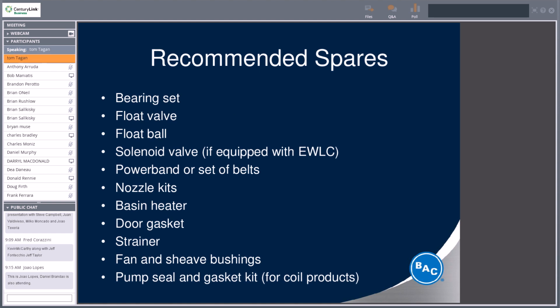Recommended spares. We recommend a bearing set, float valve, float ball, solenoid valve if you have the electric water level control, maybe a set of belts, and nozzle kits, depending on your environment. Depending on where your cooling tower is located and the quality of your water, you may decide, I haven't had to clean a nozzle in 6 years, why do I need nozzle kits on site? Which would probably be the right decision.